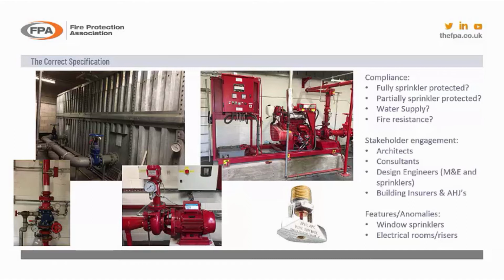And finally, features and anomalies. Recently, due to spatial separation issues in major cities, additional features such as window sprinklers have been added to the system to negate the need to increase fire resistance and glazing. Window sprinklers do not fall within any national standard. They're an added feature. They can also compromise the water supply requirements, which usually increases the capacity of the water requirement. So these additions are seen as an add-on to the sprinkler system. They won't form part of the compliance of the system, but they need to be considered.